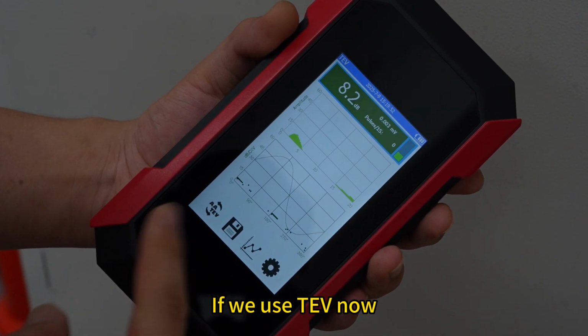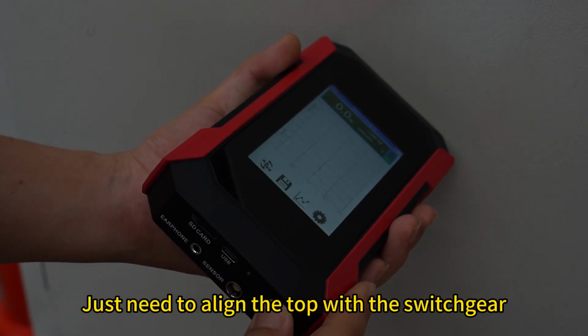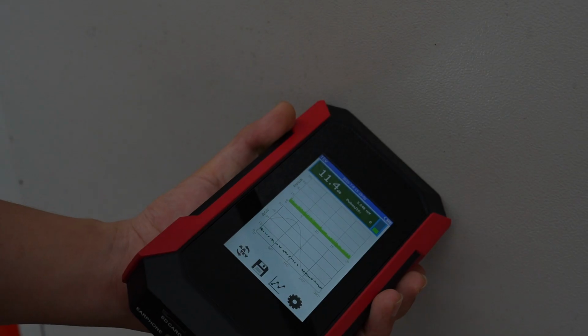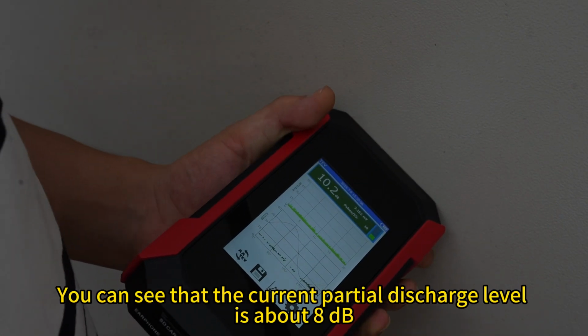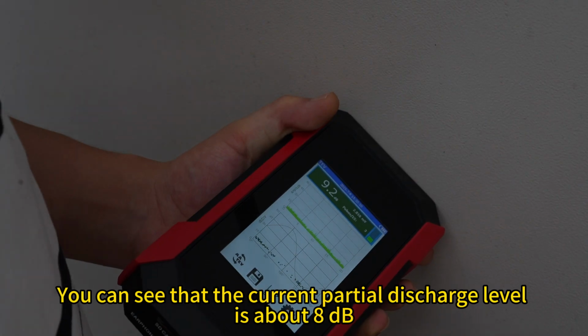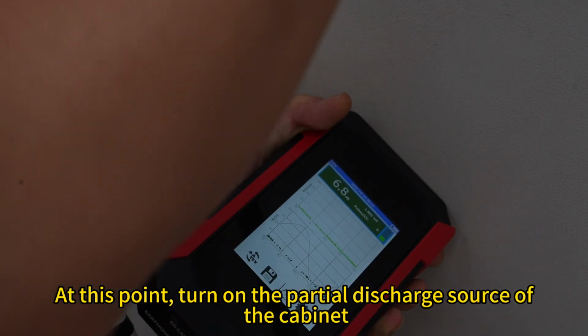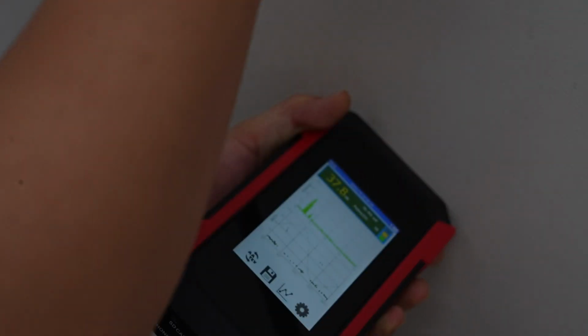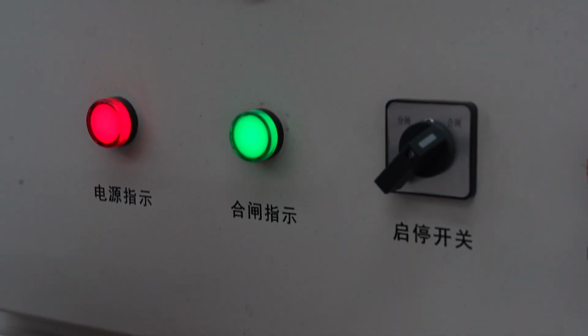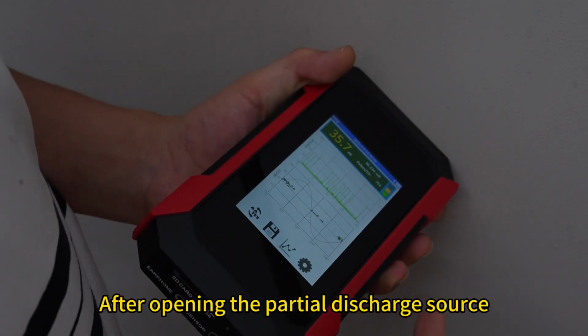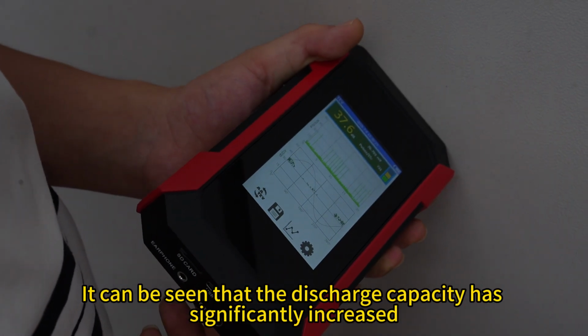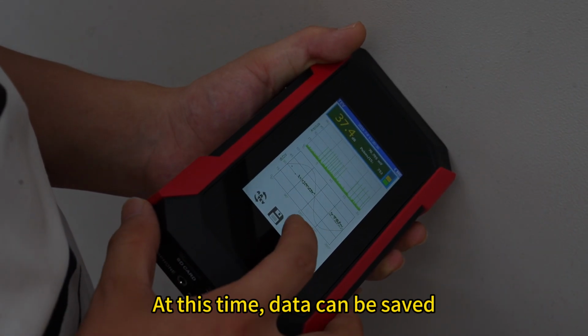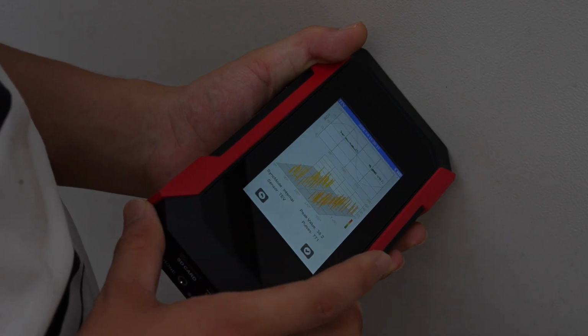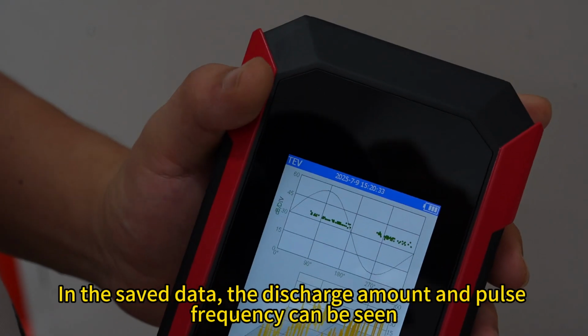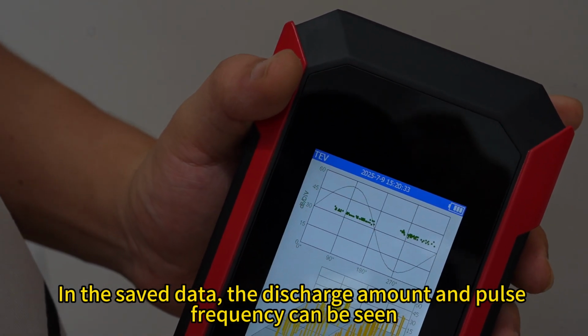If we use TEV now, just align the top with the switchgear. You can see that the current partial discharge level is about 8 dB. At this point, turn on the partial discharge source of the cabinet. After opening the partial discharge source, it can be seen that the discharge level has significantly increased. At this time, data can be saved. In the saved data, the discharge amount and pulse frequency can be seen.